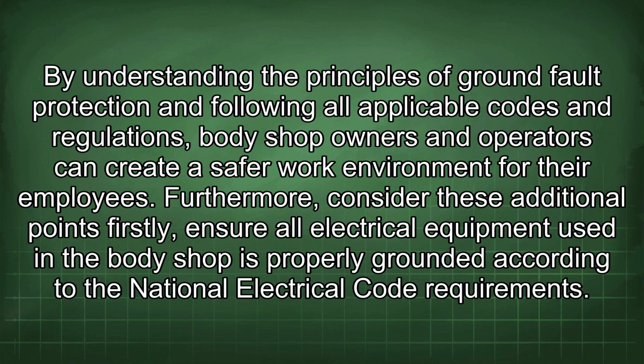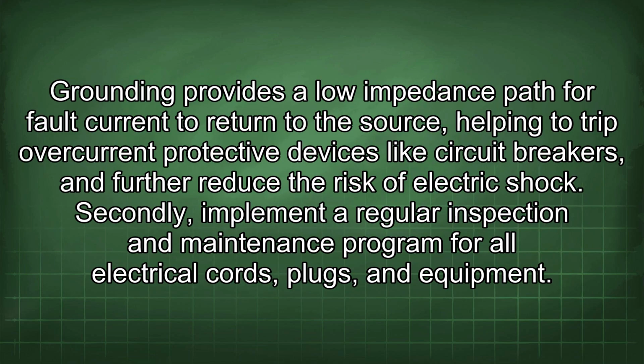Firstly, ensure all electrical equipment used in the body shop is properly grounded according to the National Electrical Code requirements. Grounding provides a low impedance path for fault current to return to the source, helping to trip overcurrent protective devices like circuit breakers, and further reduce the risk of electric shock.